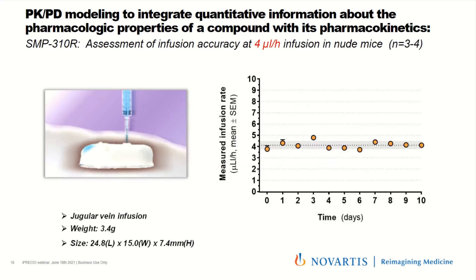To validate that the pump was delivering as programmed, we refilled the pump on a daily basis. The SMP310R in mice was set at 4 µL/hour. By measuring how much needed to be refilled each day, we calculated the actual compound delivered per hour. The results showed the pump was very consistent over 10 days of daily refilling — the observed delivery closely matched the programmed 4 µL/hour, confirming the pump was performing exactly as expected.